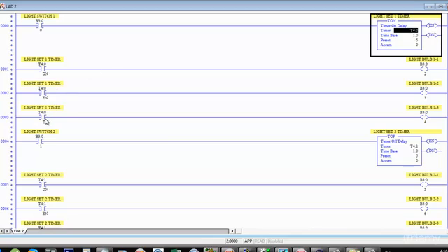Now we have this third bit, this TT bit, and TT somehow means timing. So back to square one, we flip our switch from the off to the on position, making this instruction true. Once we do, we already know what happens to our timer. It energizes, it starts counting. Well, once it starts counting, that's what timing means. So this TT bit is going to energize, and our light bulb 1-3 is going to come on.